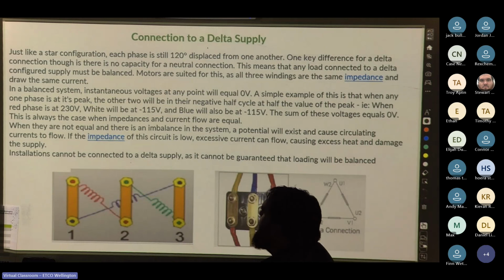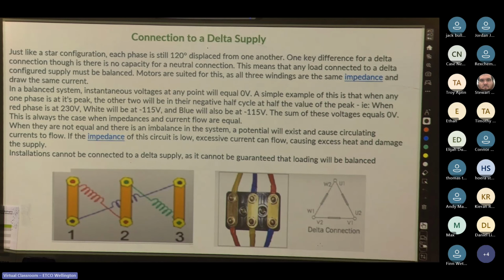Cool, so connecting to a delta supply, like a star configuration, each phase is still 120 degrees displaced from one another. The key difference for delta is that there is no capacity for a neutral connection, so any load connected to a delta configuration supply must be balanced. Motors are suited for this as all three windings are the same impedance and draw the same current. In a balanced system, the sum of the voltages at any point will equal zero. A simple example of this is that when any one phase is at its peak, the other two will be in their negative half cycle at half of the peak value. So when red phase is at 230, white will be at negative 115, and so will blue. The sum of these voltages equals zero.